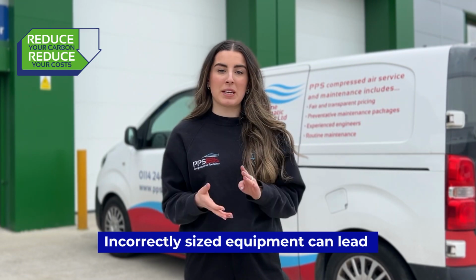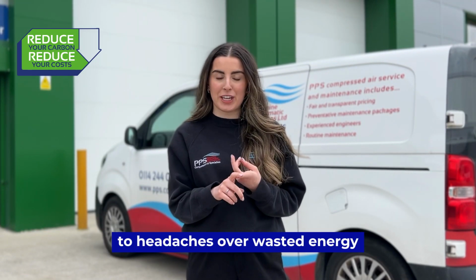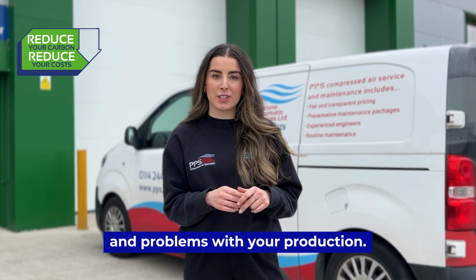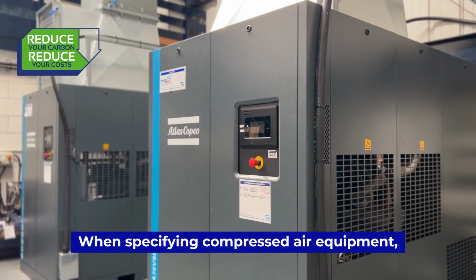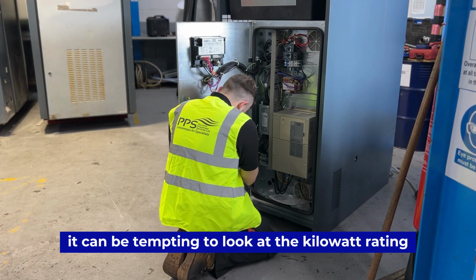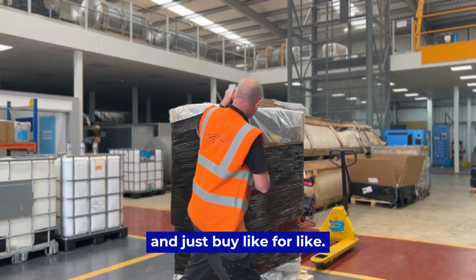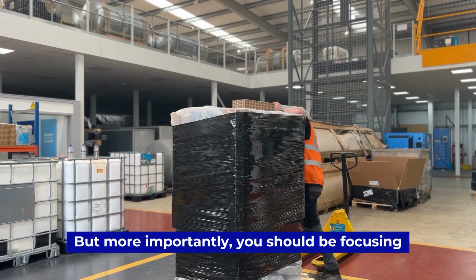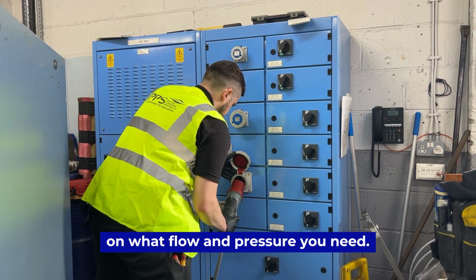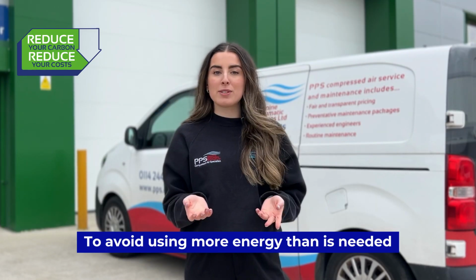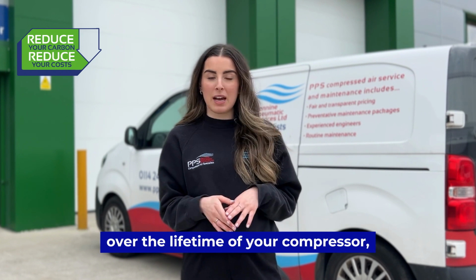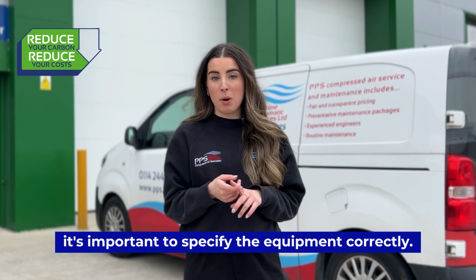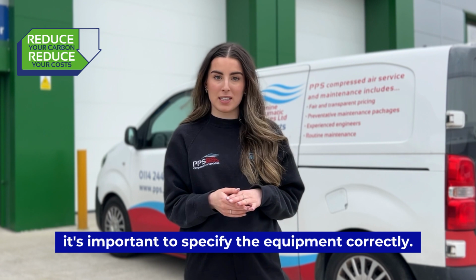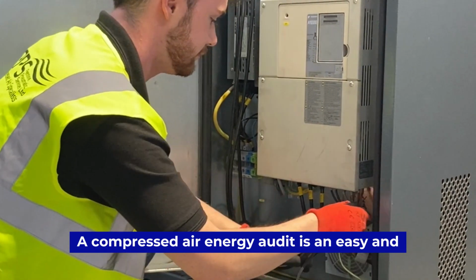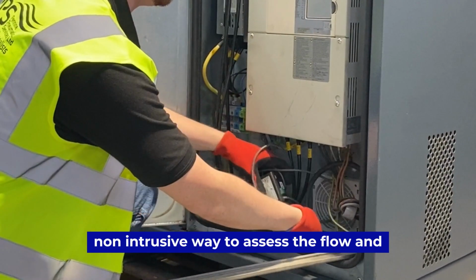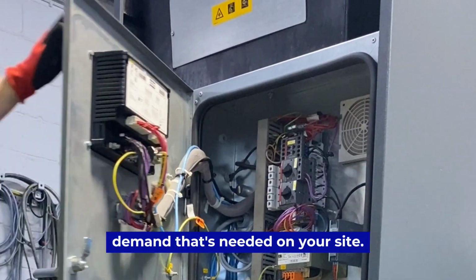Incorrectly sized equipment can lead to headaches over wasted energy and problems with your production. When specifying compressed air equipment, it can be tempting to look at the kilowatt rating and just buy like for like. But more importantly, you should be focusing on what flow and pressure you need. To avoid using more energy than is needed over the lifetime of your compressor, it's important to specify the equipment correctly.